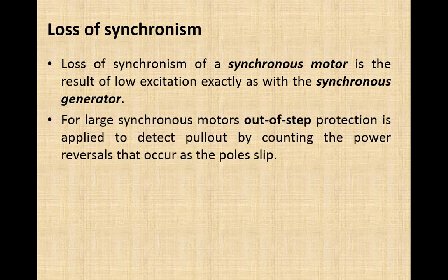For large synchronous motors, out-of-step protection is applied to detect pull-out by counting the power reversal that occurs as the pole slips. When we have loss of synchronism of synchronous motors, the rotor magnetic field pole will start slipping over the stator magnetic field, and that will result in pulses of power reversal.